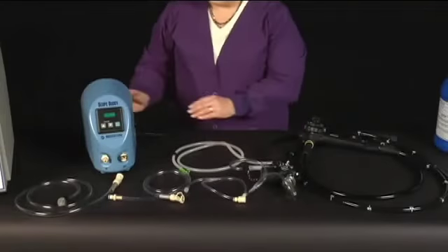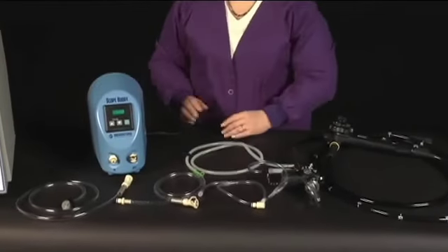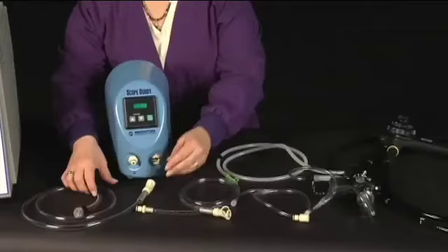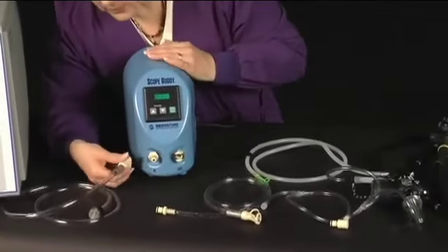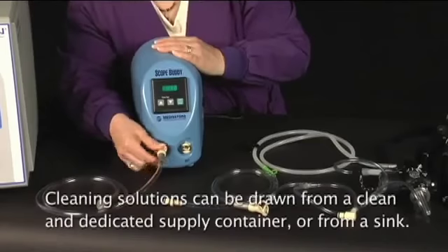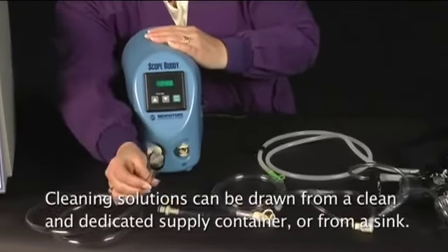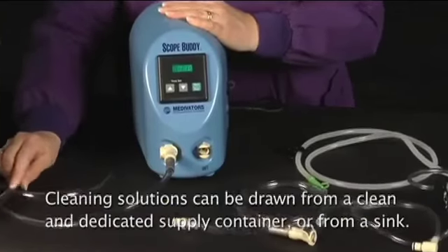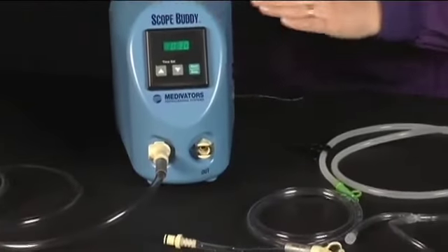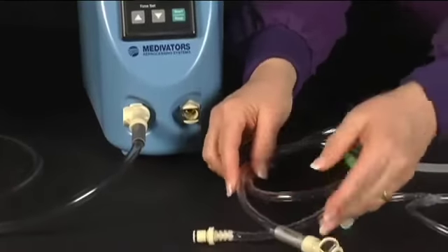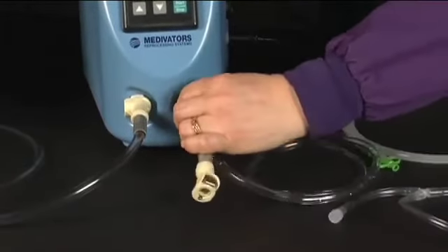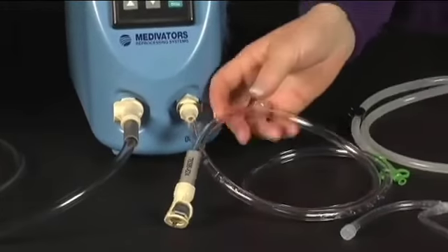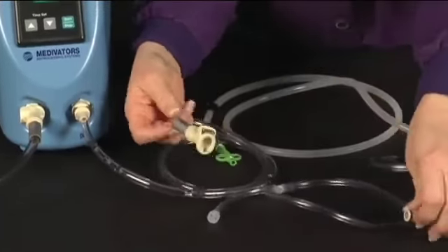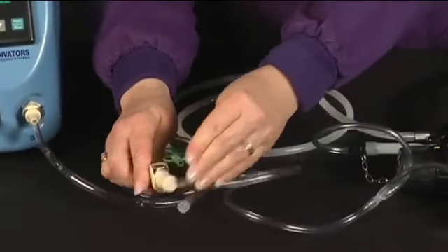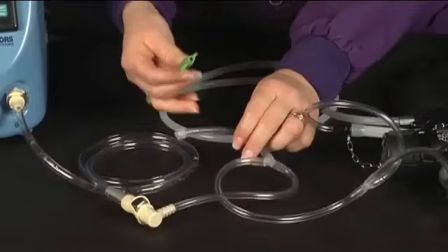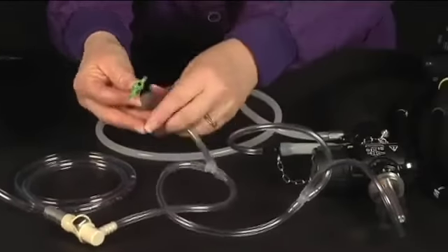Plug the unit in and turn the device on by pressing the power switch. Snap the connector of the fluid intake line to the connection port labeled in and fully submerge the screened end in a sink or clean supply container of detergent solution. Snap the connector of the DSD extension line to the connection port labeled out. Attach the remaining end to the appropriate DSD hookup for the endoscope being cleaned. Attach the DSD hookup to the endoscope, referencing the hookup instructions if needed.